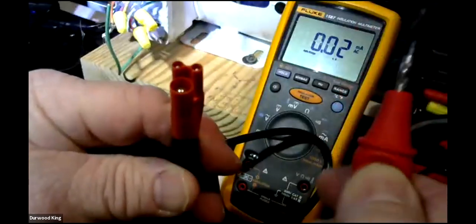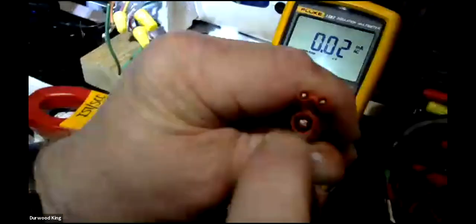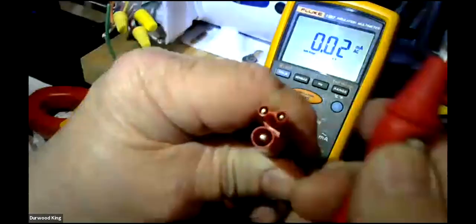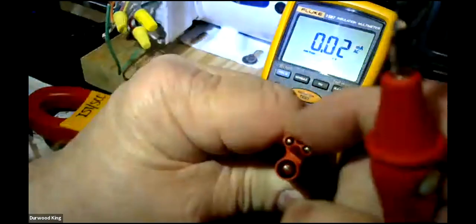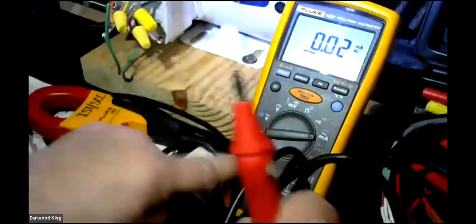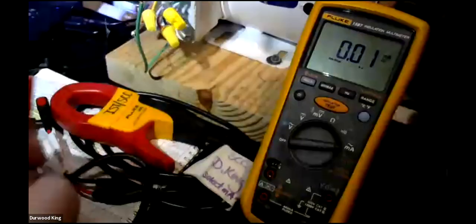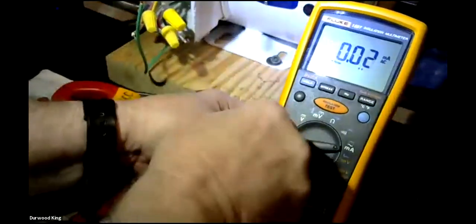Now, you see that probe right there? That probe there has a button on it that you press to test it with. It's just one cable there, but it has a high voltage thing, and then these two little things is actually the button. You press the button, it actually makes those two right there together, and it tells the meter to shoot voltage up that line there. Okay, so it goes over to here. It goes in that special jack over there. So let's plug into that, and so it goes right in there like that on the left. That's where your high voltage probe goes. It produces voltage on this and shoots it into the motor.